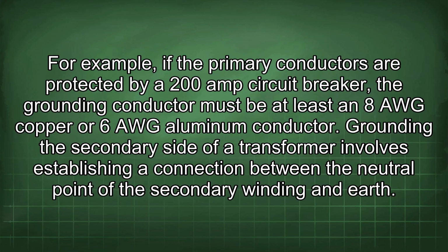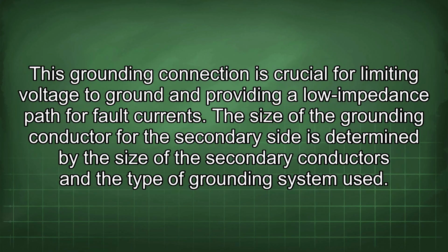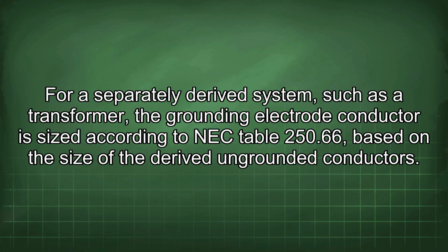Grounding the secondary side of a transformer involves establishing a connection between the neutral point of the secondary winding and earth. This grounding connection is crucial for limiting voltage to ground and providing a low impedance path for fault currents. The size of the grounding conductor for the secondary side is determined by the size of the secondary conductors and the type of grounding system used. For a separately derived system, such as a transformer, the grounding electrode conductor is sized according to NEC Table 250.66 based on the size of the derived ungrounded conductors.